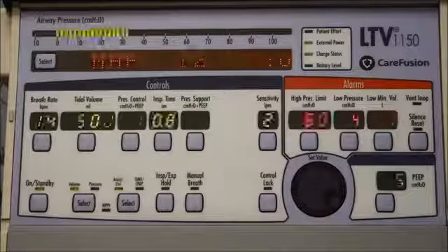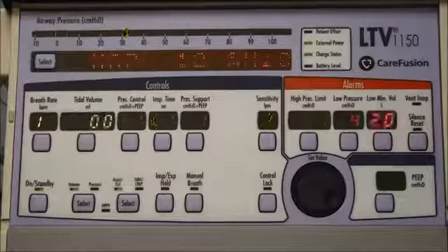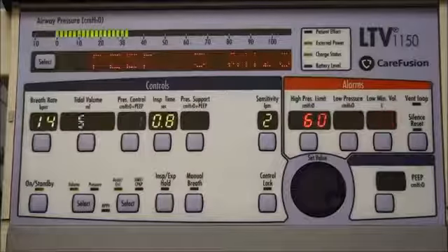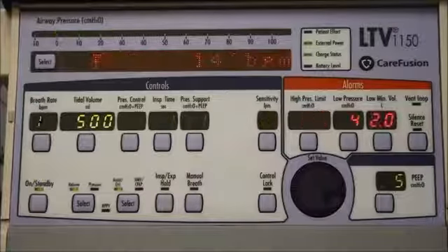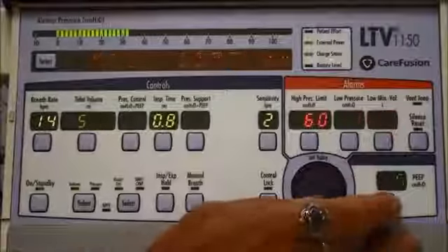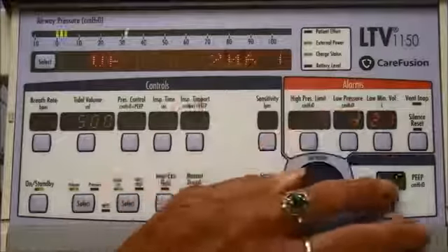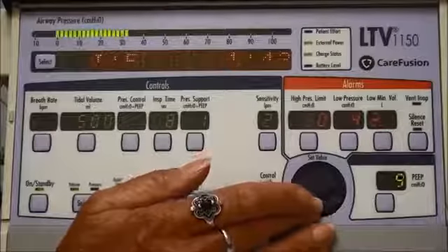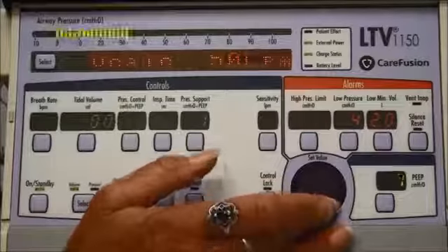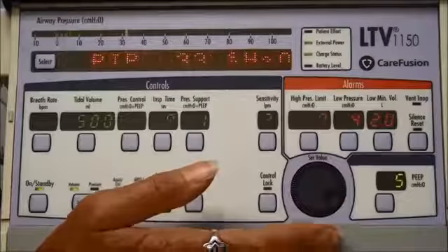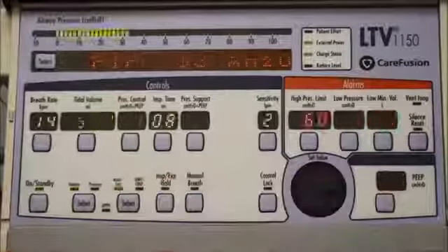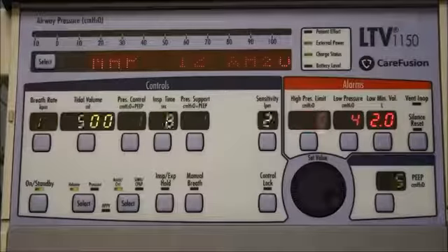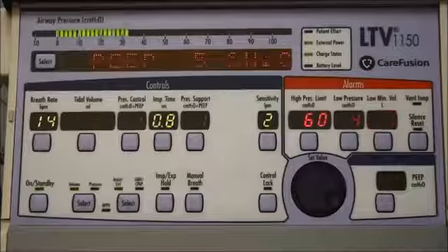To set your PEEP, you're going to want to make sure that you have your patient off the particular ventilator that you're setting. You're going to hook up your test lung. Then you're going to come over here and push this button, and you'll see everything blank out except the PEEP. Then I will take my set value knob and turn it to whatever I want my PEEP set at according to the orders. I push that button again, it'll lock it in. So it's very easy to do.